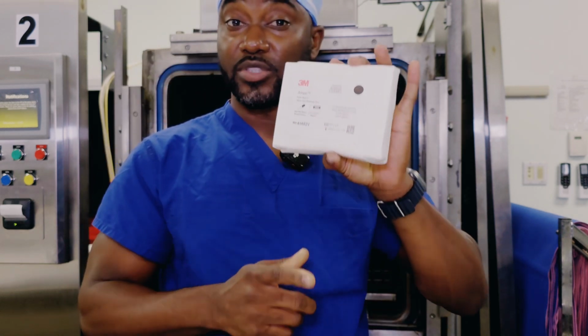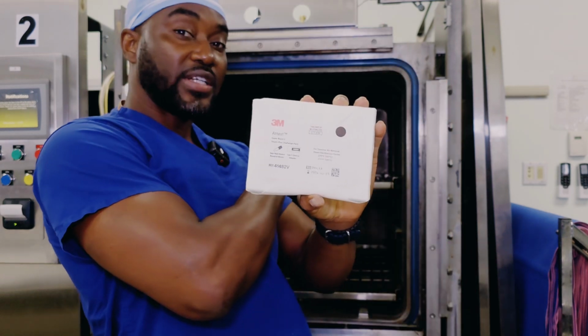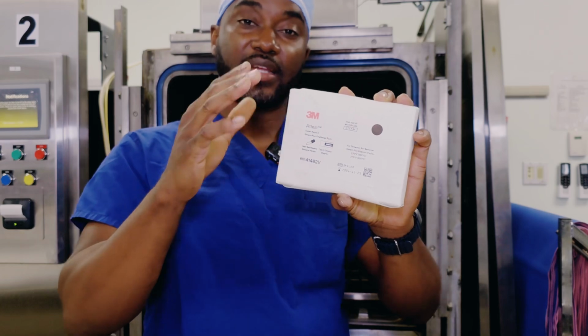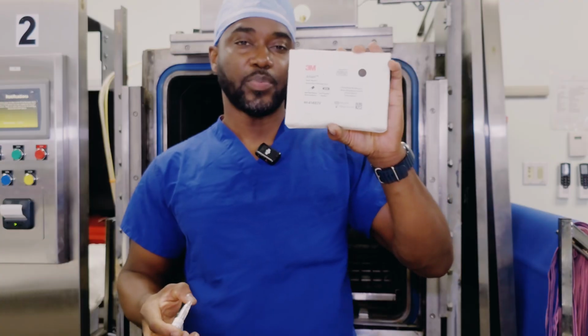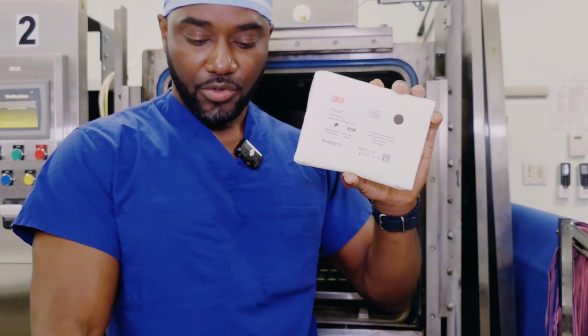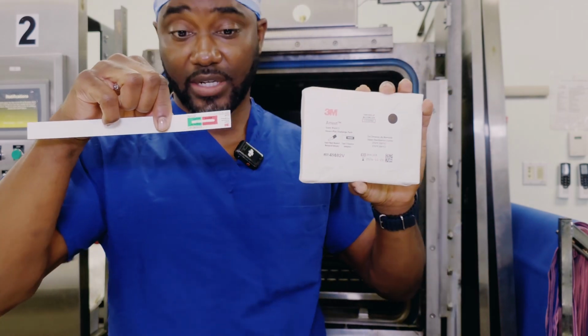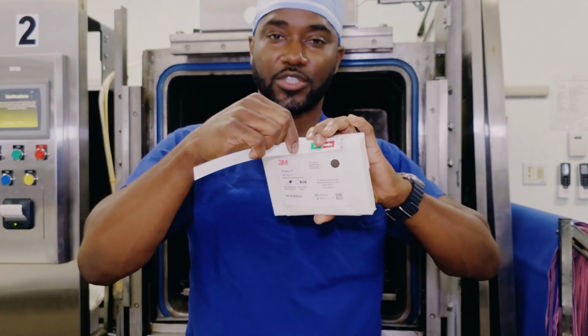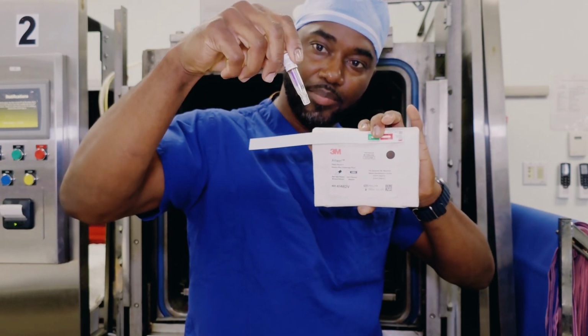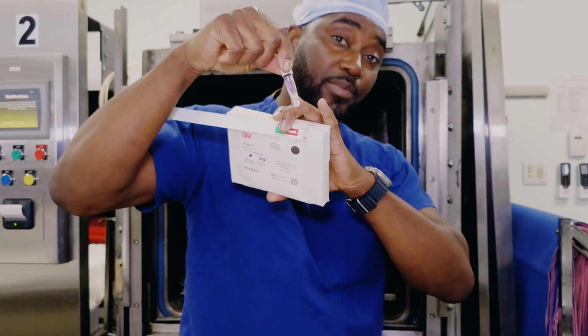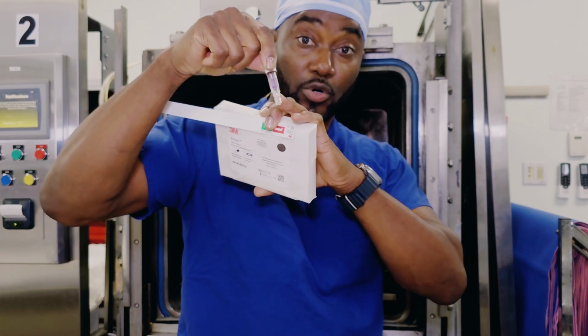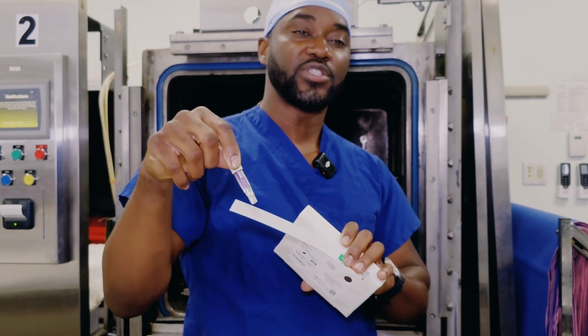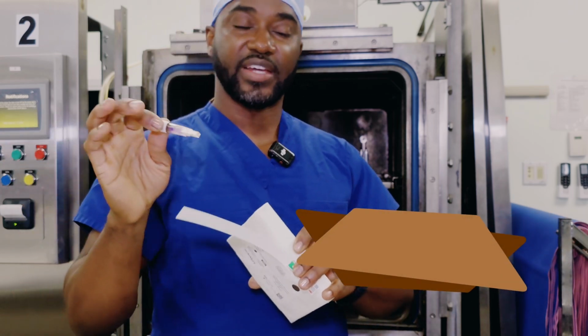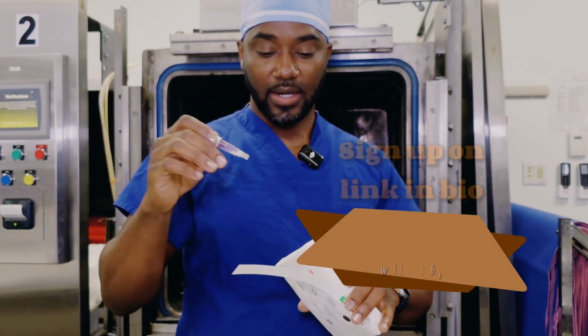For testing purposes, this was run on a rejected cycle, so we just wanted to make sure that it's not working properly. Within this process challenge device, you have a type 5 chemical integrated indicator. You also have a biological ampoule that is loaded with a Geobacillus stearothermophilus spore. This is the spore of choice for all sterilization cycles, with the exception of ethylene oxide, which uses Bacillus atrophaeus.